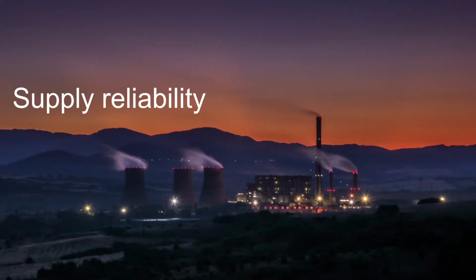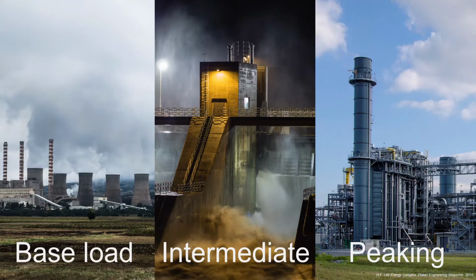We need supply reliability, which means dispatchable generation to meet demand not fulfilled by variable generators. In our power system, we have different types of generators that serve different purposes. Baseload power is the unvarying generation which occurs the majority of the time. These have low operating costs and like to run at a steady output, such as nuclear or coal-fired plants. Peaking plants, typically natural gas-fired peakers, are expensive to run but able to respond quickly to system demand.